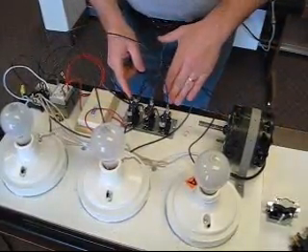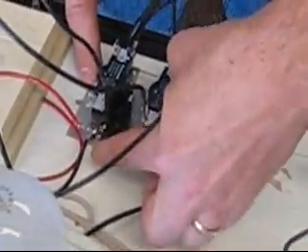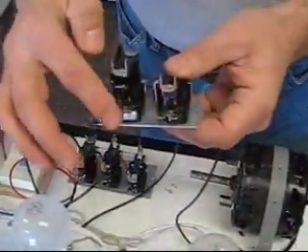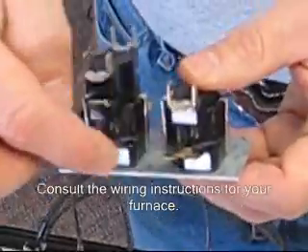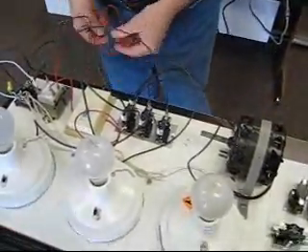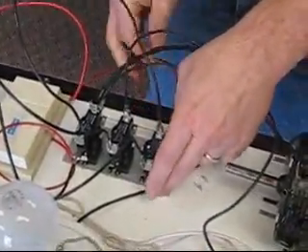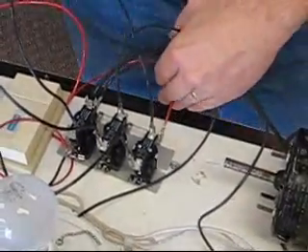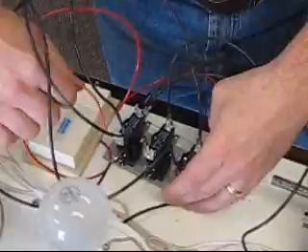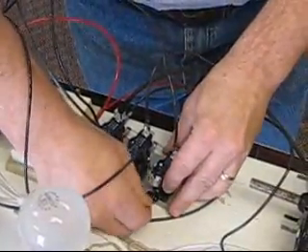Now sequencers are operated by 24 volts. And that's the bottom one. On this one, if you can zoom in, we have a bar that's welded here that connects all the 24 volt terminals. Versus this one, there is no bar. So you'd want to put a jumper in there. Or consult the wiring diagram of your furnace. So we take our 24 volts from our transformer. We hook one on one side. Doesn't matter which terminal on this side as long as it's on this side. And then the other 24 volt goes through our thermostat. And then it comes out of our thermostat. And then we hook it to the bottom of the other side of the sequencer.